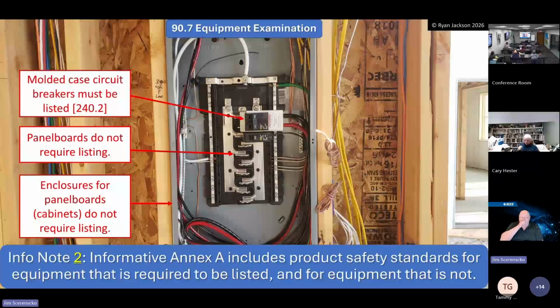Tammy? Is there some kind of basic philosophy on what determines what products have to be listed and which do not? I think if you look in the electrical code itself, it basically says everything in that book that talks about installing shall be listed. Okay. Not all of it is labeled. So everything has to fall under a standard. But again, it doesn't have to be labeled. A perfect example is EMT. EMT has to be listed, but the label doesn't have to be on each stick of EMT.